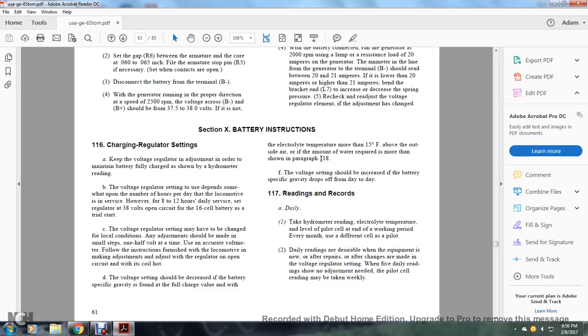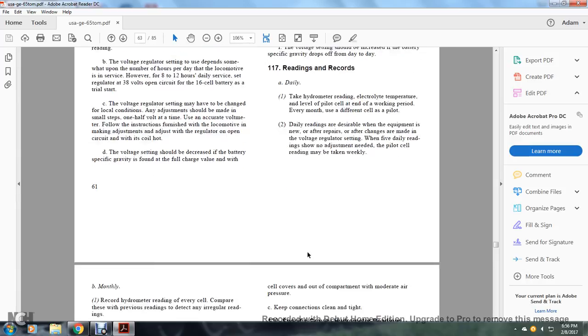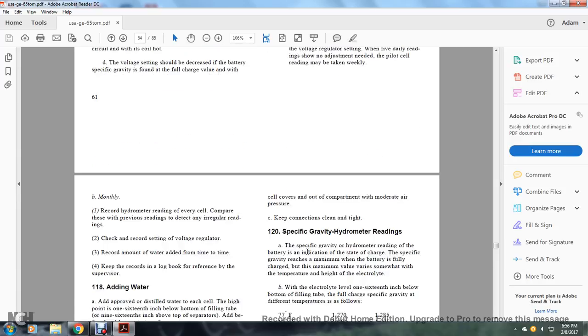Reading and records: Take daily hydrometer readings of the electrolyte temperature level by the pilot cell at the end of the working period. Use a different cell as pilot every month. Daily readings are desirable when equipment is new, after repairs, or after changes are made. With five-day readings showing no adjustment is needed, the pilot cell reading may be taken weekly. Monthly records of hydrometer readings for every cell should be compared with previous readings to detect any irregularities.